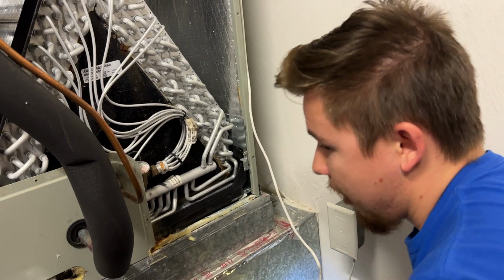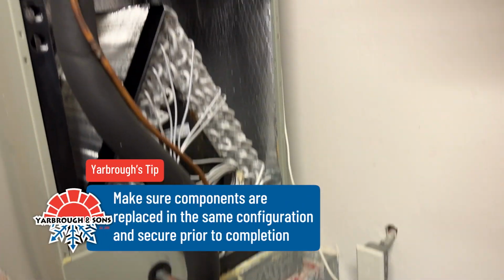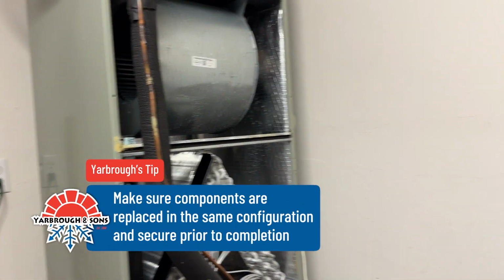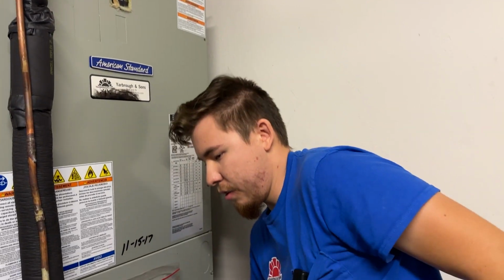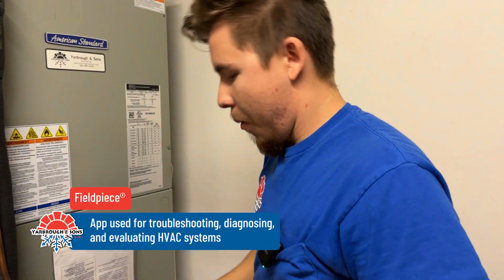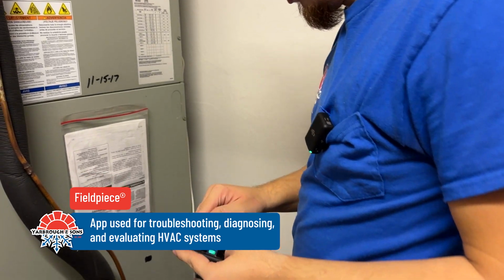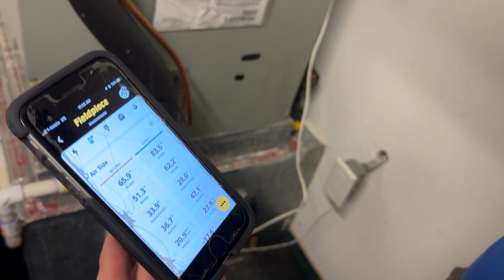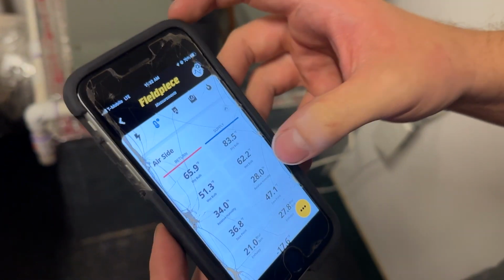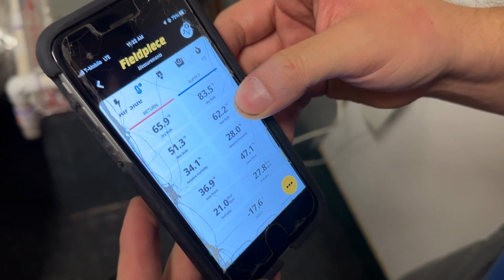So we've got that in. I'm going to go ahead and button these doors on real quick, so we get a more accurate temperature split difference. Now we get on our Fieldpiece app. We're going to look at our delta T, our temperature difference. So we're pushing about 83 degree air out right now, but with it just now kicking on, we're going to have to let it run for about 15 minutes.